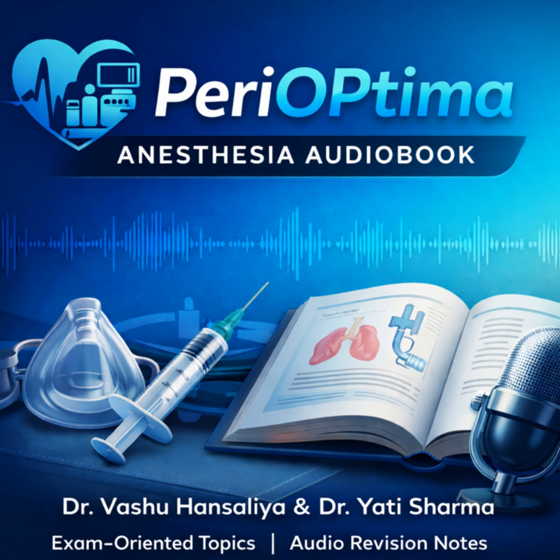So for that patient, the dependent patient with an ICD undergoing surgery with heavy cautery, a magnet is not enough. It is not sufficient. For that high-risk patient, the gold standard is to have a cardiology technician come and formally reprogram the device. They will turn off the tachytherapies and set the pacing mode to a non-sensing asynchronous one like VOO. And if there's no time for that, then you must have external pacing pads on the patient and be ready to use them the instant you see inhibition on your arterial line.